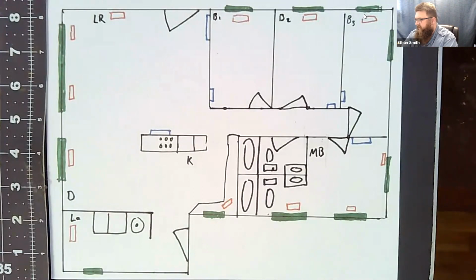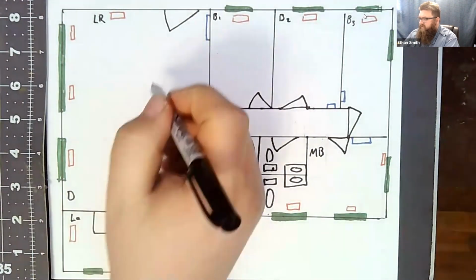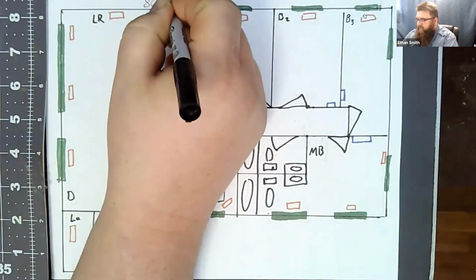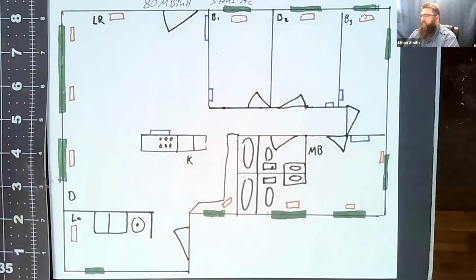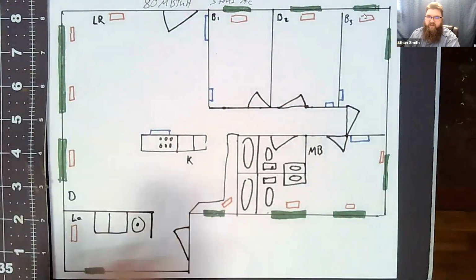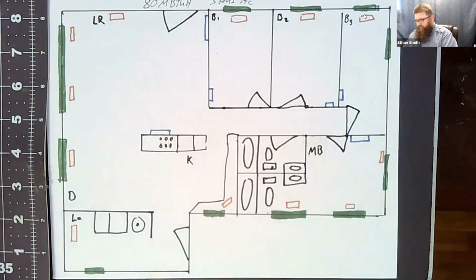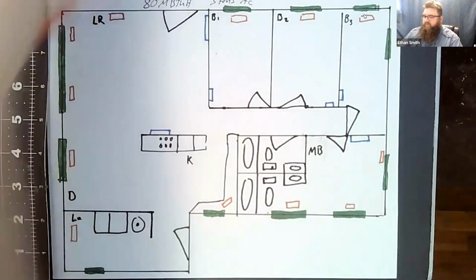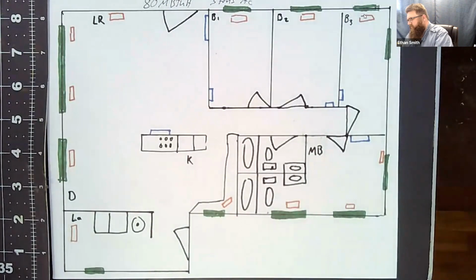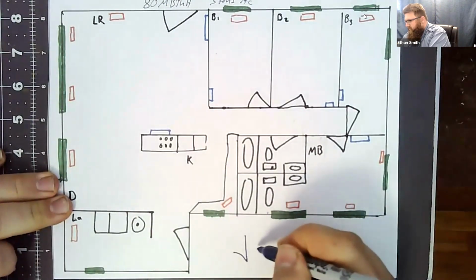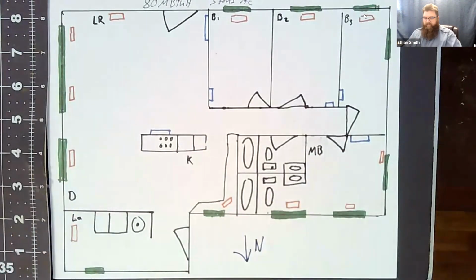We're getting roughly 120 CFM out of each vent in this case, and my load is 80,000 BTUs. And 3 tons. Okay, so there's my load on the house. How would you guys zone this? It can be zoned a number of different ways. Oh, I got to give you a north-south too. Someone give me a zone. What would you include in your first zone?